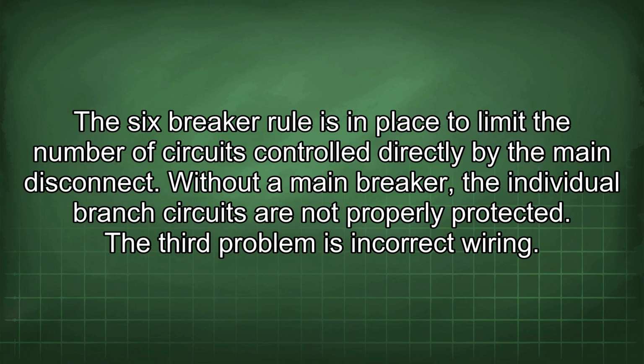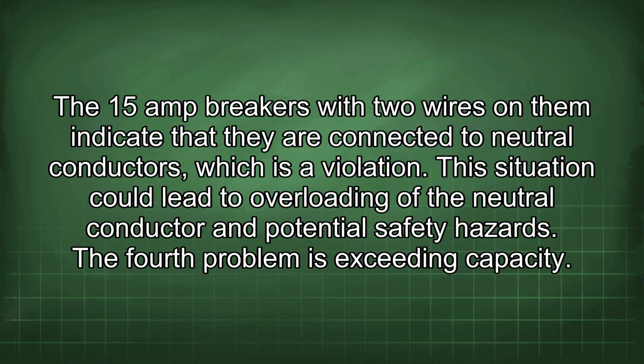The third problem is incorrect wiring. The 15 amp breakers with 2 wires on them indicate that they are connected to neutral conductors, which is a violation. This situation could lead to overloading of the neutral conductor and potential safety hazards.